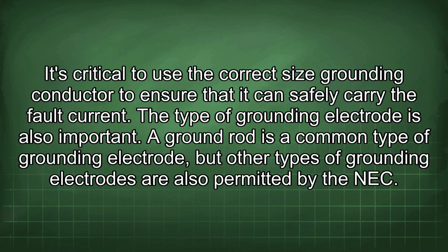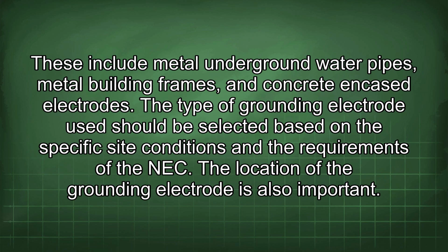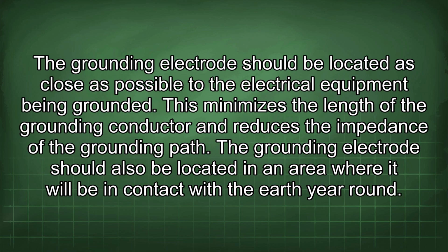The type of grounding electrode is also important. A ground rod is a common type of grounding electrode, but other types of grounding electrodes are also permitted by the NEC. These include metal underground water pipes, metal building frames, and concrete encased electrodes. The type of grounding electrode used should be selected based on the specific site conditions and the requirements of the NEC. The location of the grounding electrode is also important. The grounding electrode should be located as close as possible to the electrical equipment being grounded. This minimizes the length of the grounding conductor and reduces the impedance of the grounding path.